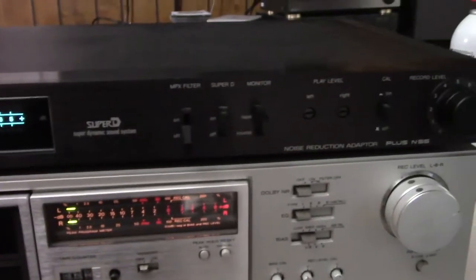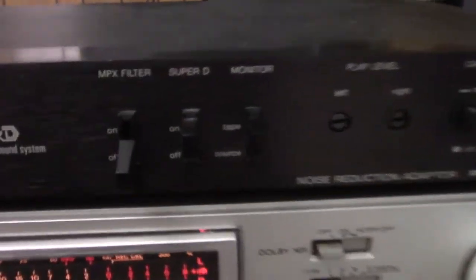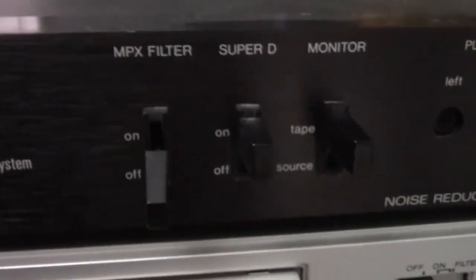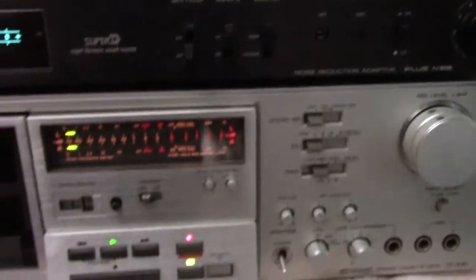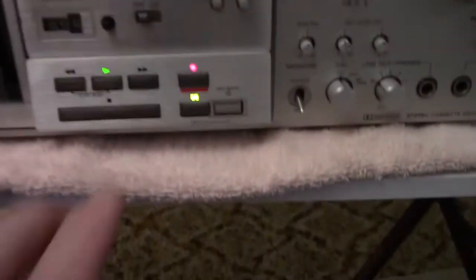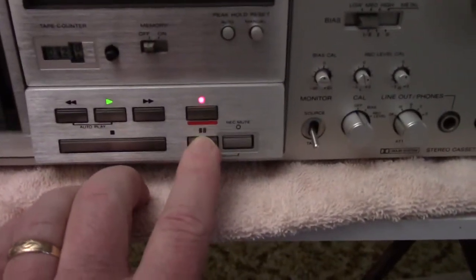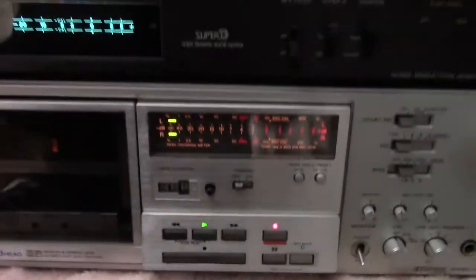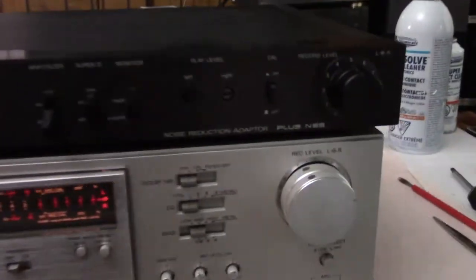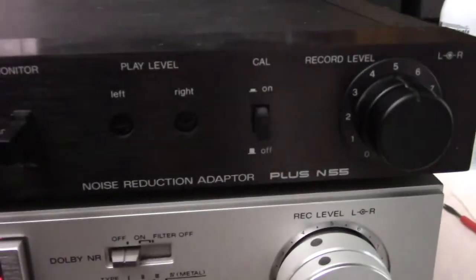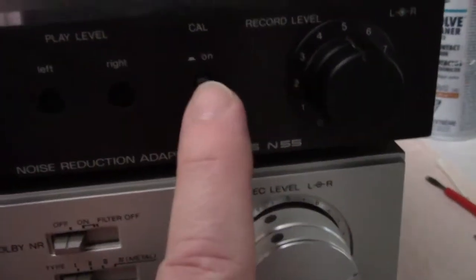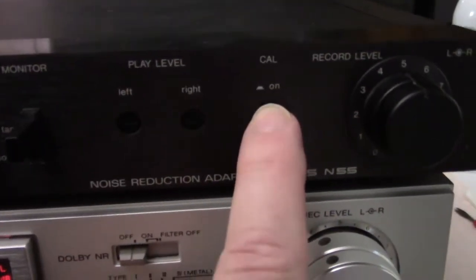And what I'm going to do is we're going to put it through its calibration mode here. And to put it into calibrate, what you've got to do is have it in tape mode and Super D on. Okay, so I'm going to start the tape rolling. The tape is rolling now. Okay, and to start from there, we go into cal, this button here. We turn on the cal tone.